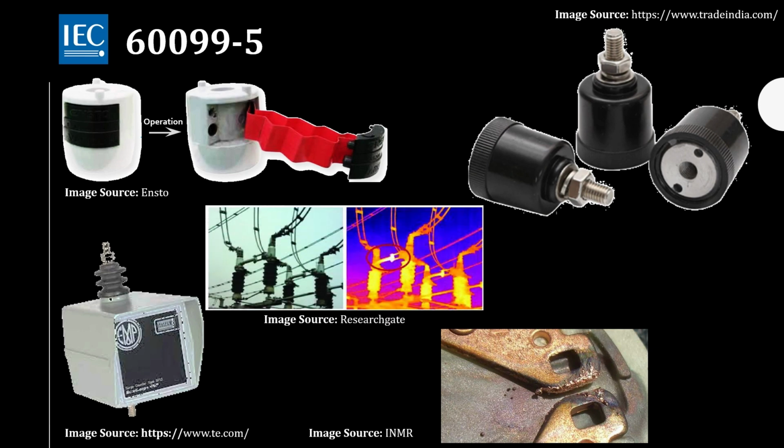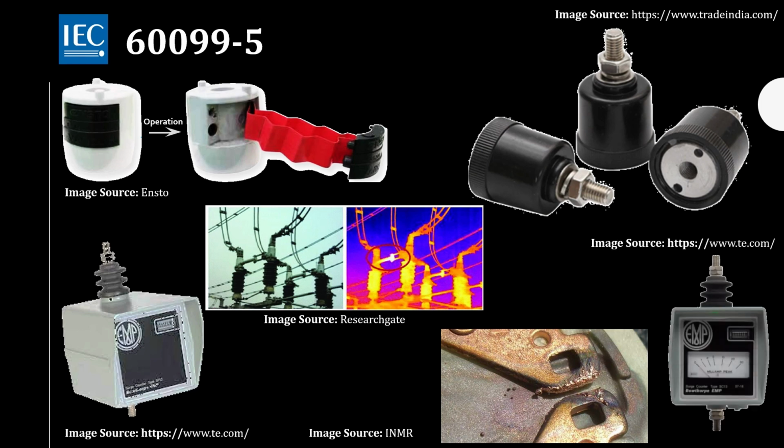The fifth one being temperature measurement using thermal camera to verify the temperature of the arrestor as well as identify the hotspots. This method relies a lot on comparative measurement. And the sixth one is leakage current measurement, which is the most followed diagnostic indicator.